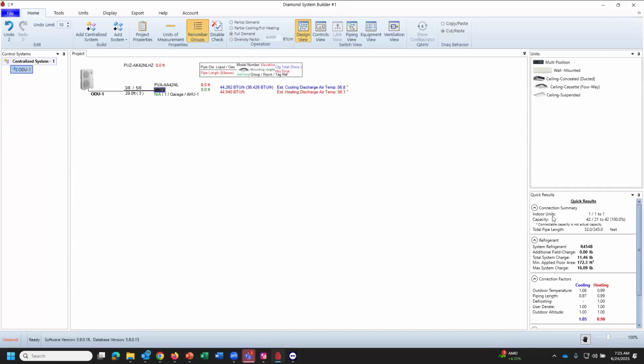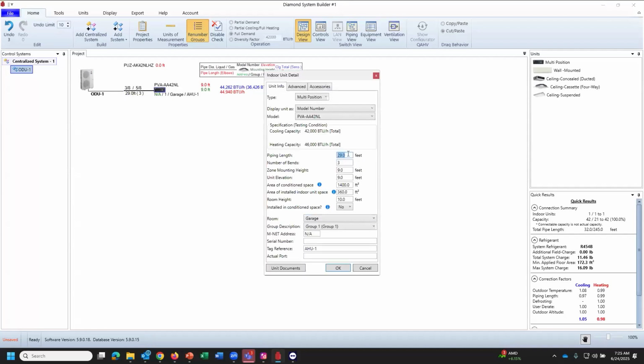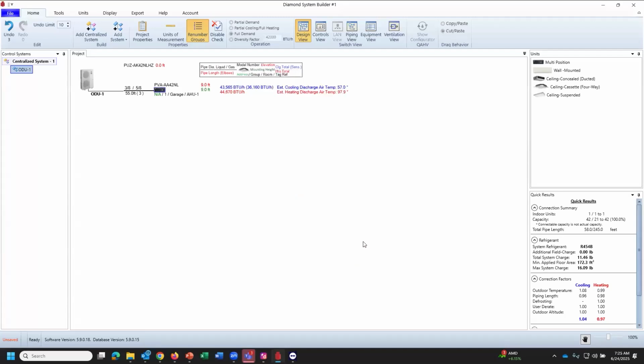So in this situation, we can have a lot of charge. This particular one, I believe, is charged up to 50 feet. So let's say 55 feet here. And we still have no additional charge needed on here. So let's kick this out even further. Say the homeowner decides that he wants to put the outdoor unit way out in the middle of nowhere and pipe underground. We're going to increase this out to 150 feet and we're going to throw 12 bends at it. At that point, we start seeing some additional charge calculated in here.